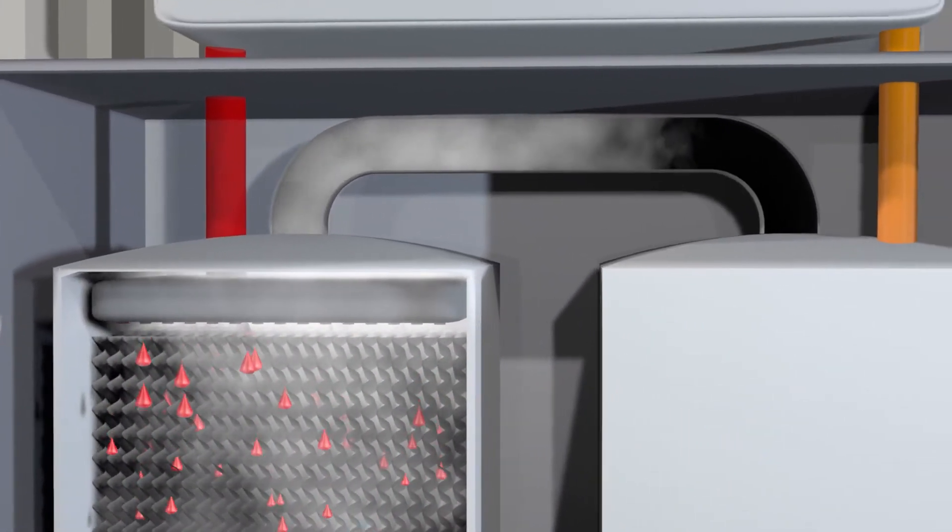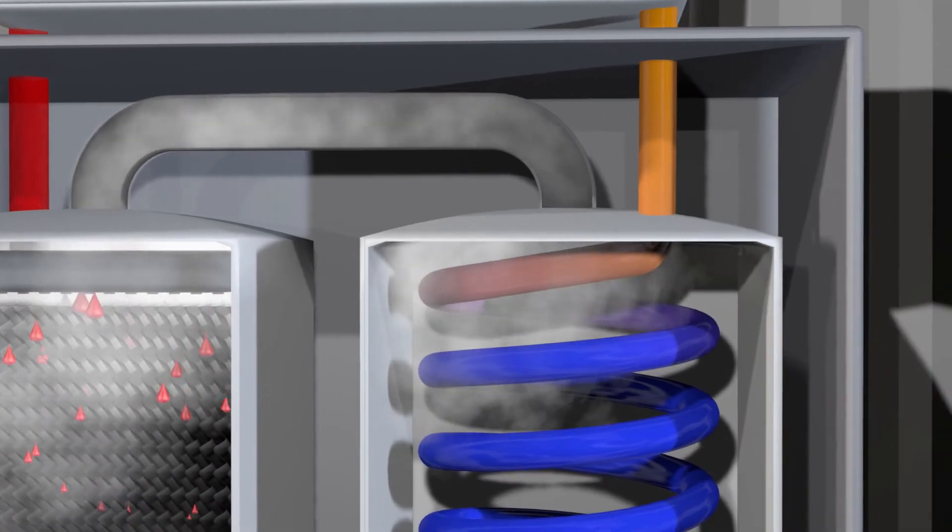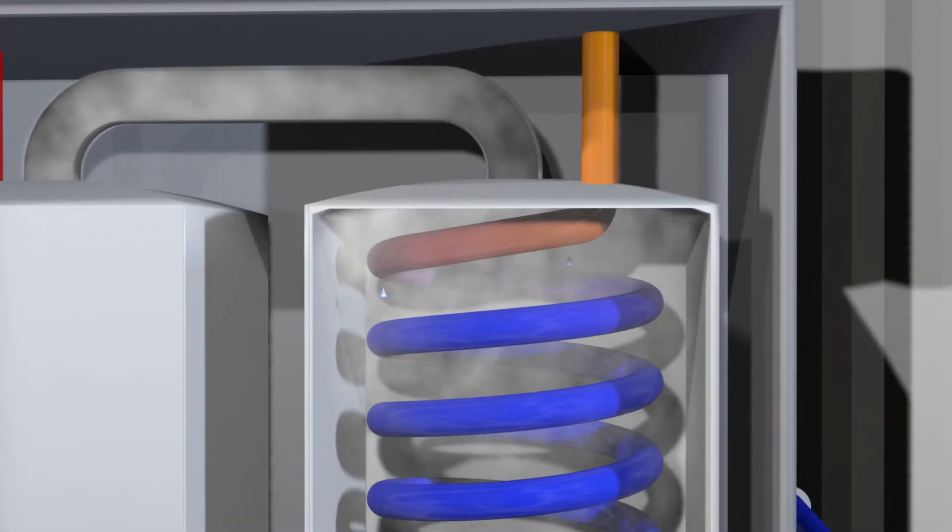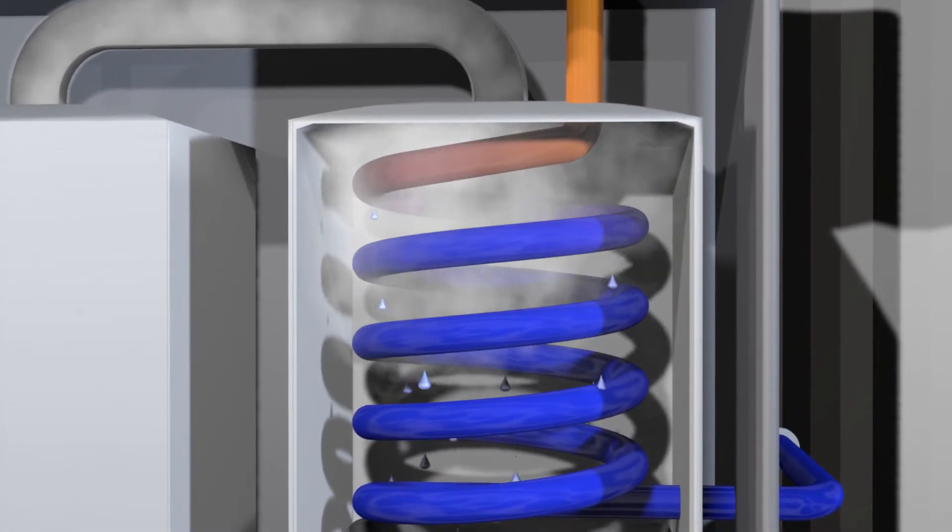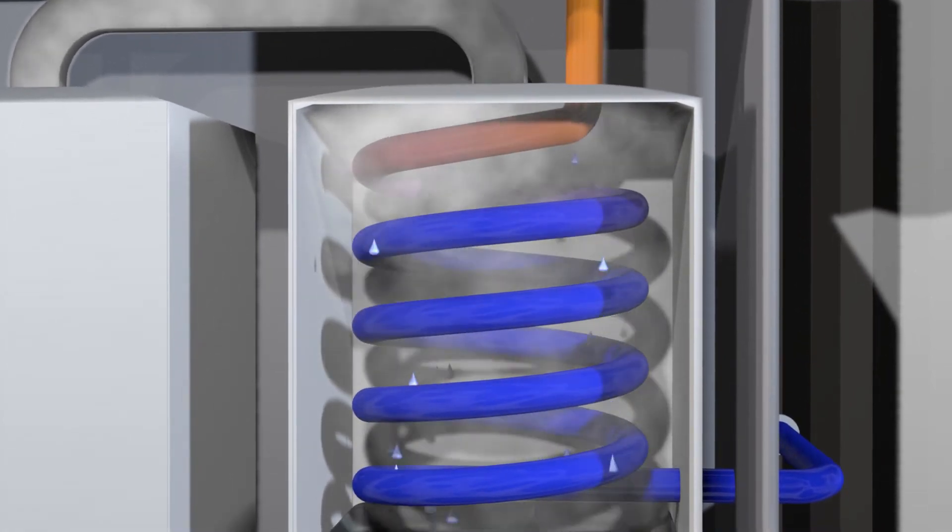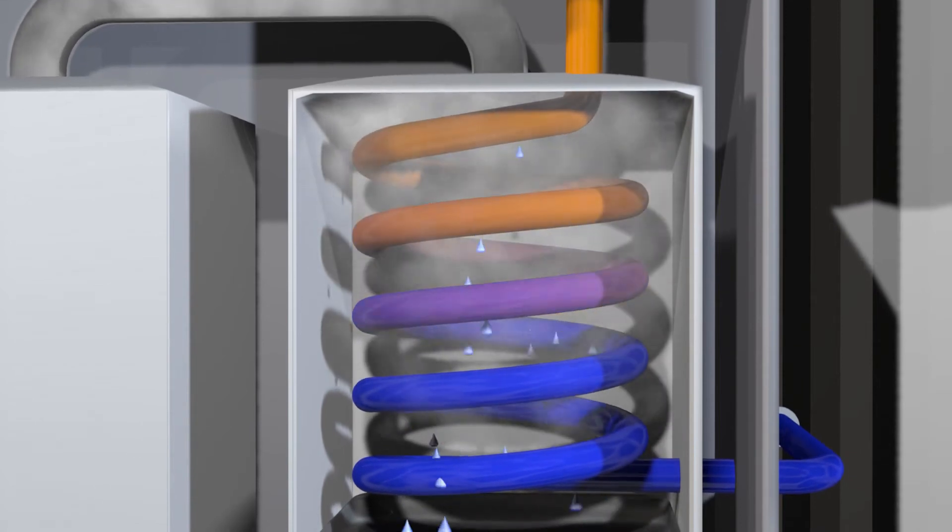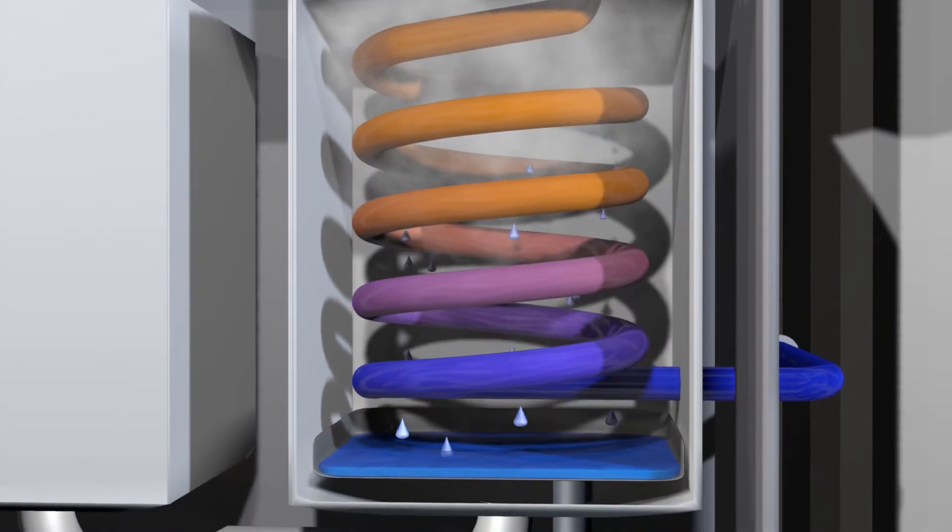The water-saturated air flows into the condenser. Here it cools at the tubes filled with cooler raw water. Water condenses. At the same time, the condensation heat is used to preheat the untreated water in the tubes. This increases the efficiency of the system.